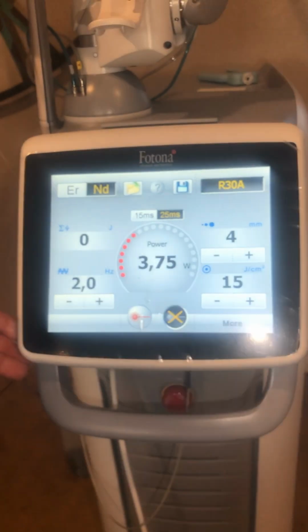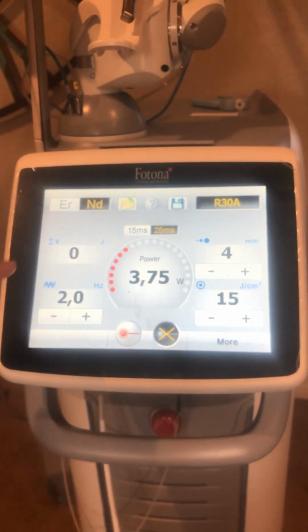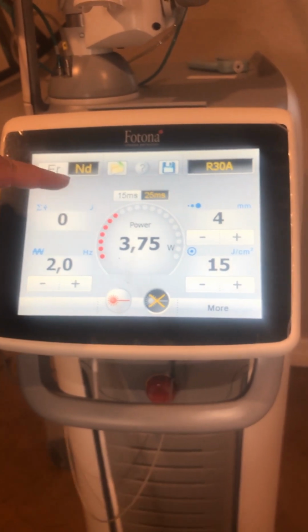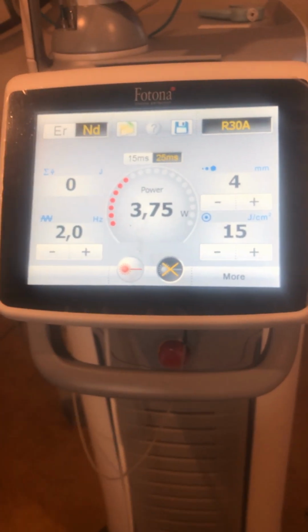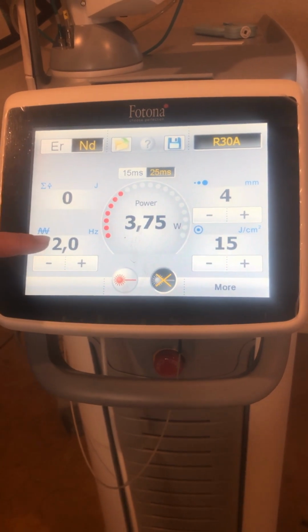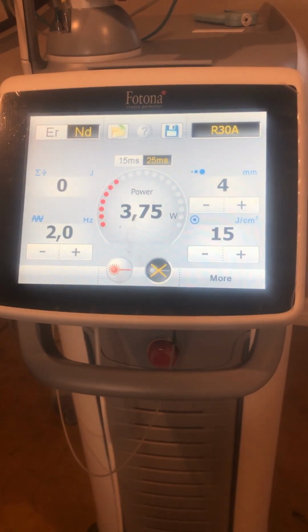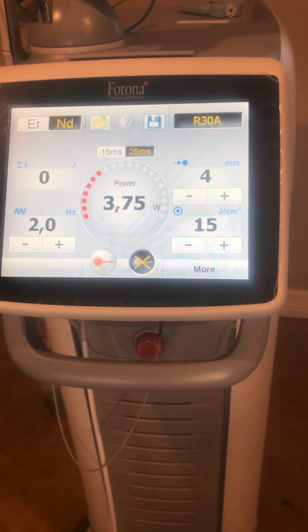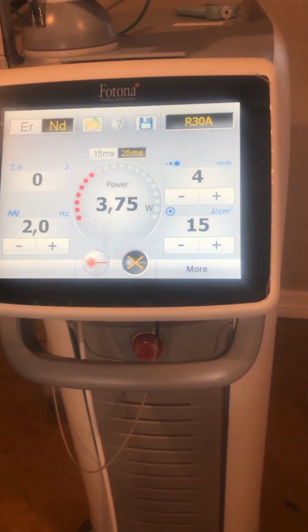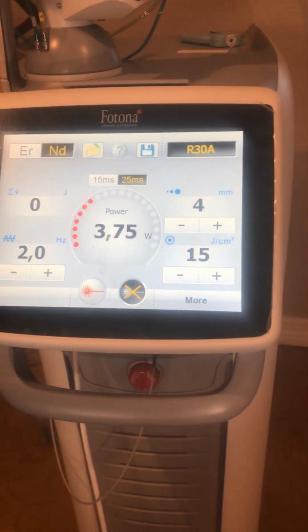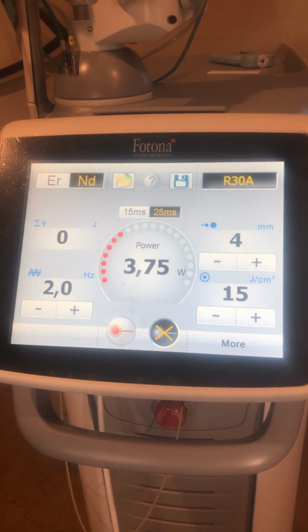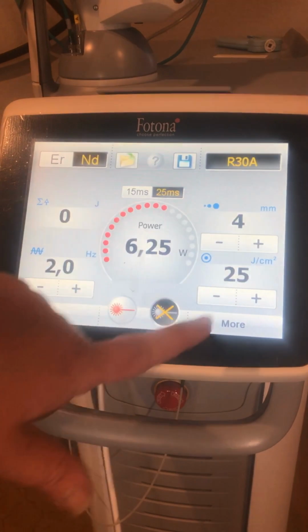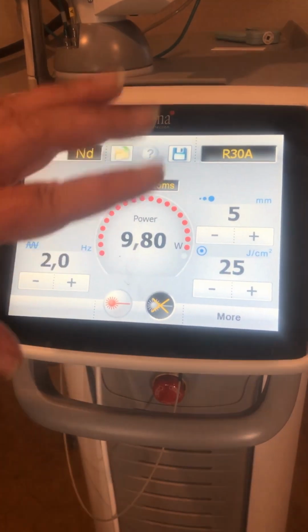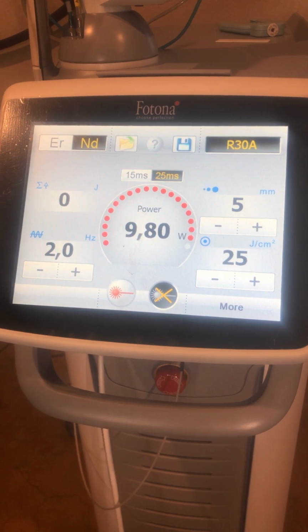And then let's look over here on the screen. So when you're working with this setting with the R30A, you're going to notice the screen looks a little different. Instead of having your normal pulse durations, you're going to have 15 milliseconds and 25 milliseconds are the only choices that you can do. You're still going to have your hertz to be able to adjust, and you're going to have your joules per centimeter squared, which will give you your wattage change or your power change. The other thing is you're going to have a new item instead of, like the other handpieces, you have a spot size. So these little circles there, that is representing spot size change. And as I change the spot size, it's going to change the power setting on there. So if you notice, when I go up to the different spot size, it changes the energy. So it's really important that you have your spot size appropriate for the procedure that you're going to be doing.